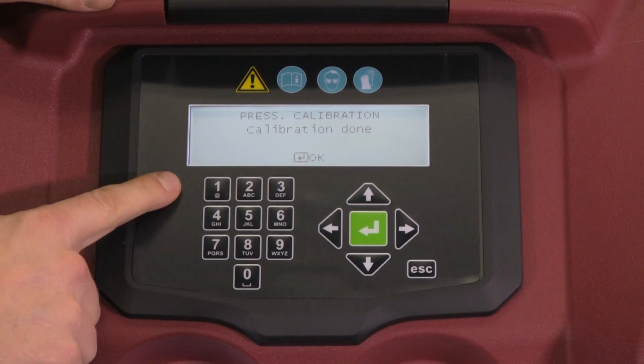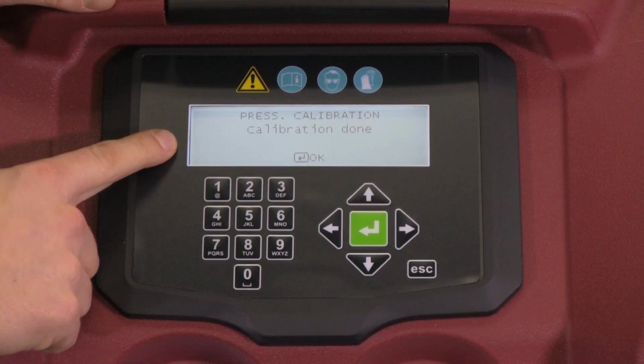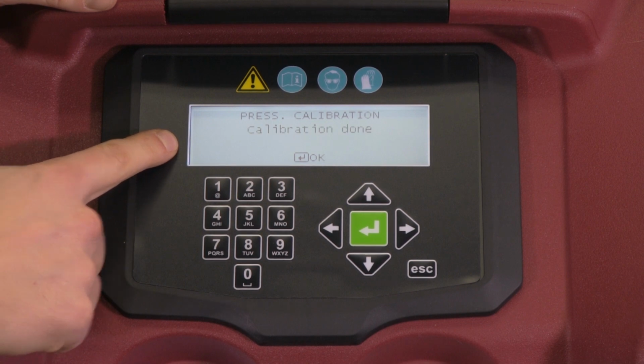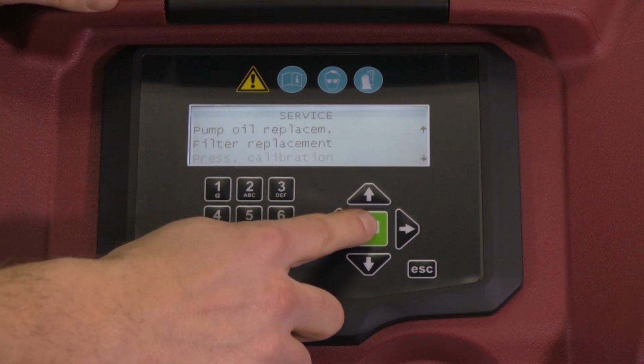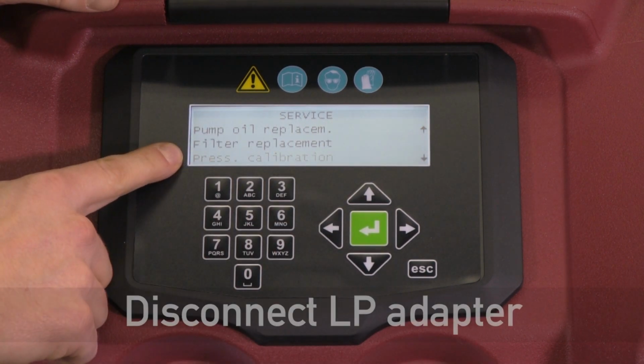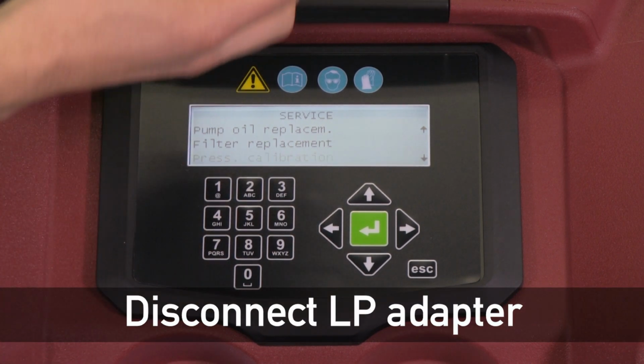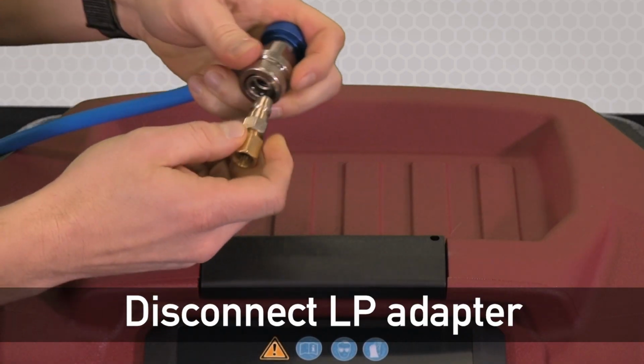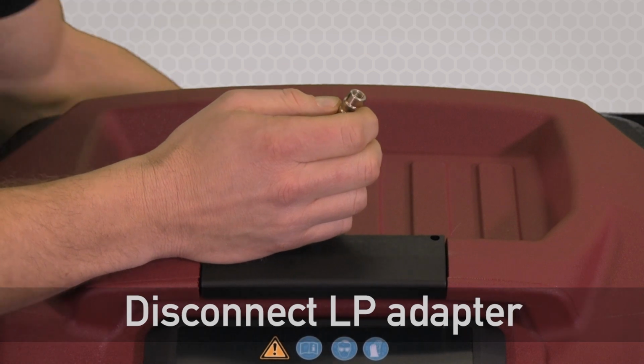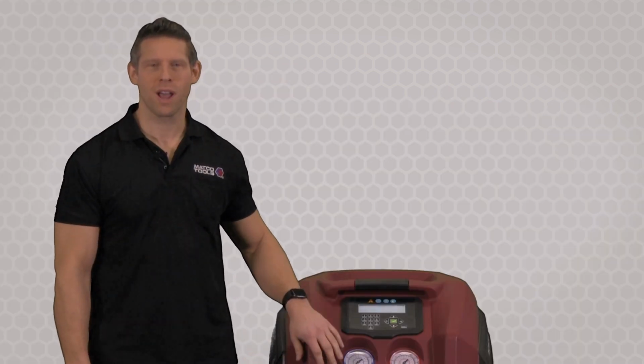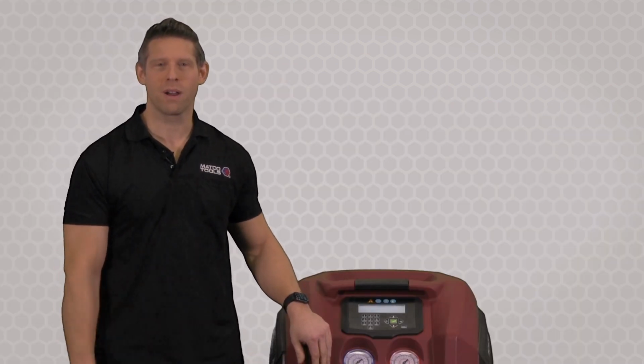We've now finished the vacuum phase of this after the pressure drain, and the calibration is done. Now I can hit OK, and it'll take me back to the menu. Remember to disconnect your LP adapter and place it in the basket for safekeeping. That completes the pressure calibration demonstration for this Matco AC438.